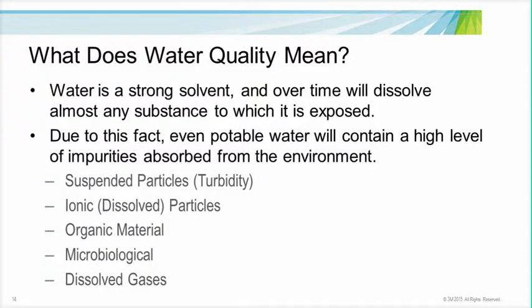In the healthcare industry, when we talk of water quality, we are referring to water with a reduced level of impurities as that of potable or drinking water. Because of its strong solvent characteristics, water inherently contains a myriad of impurities absorbed from the environment. We categorize these impurities as suspended particles, ionic or dissolved particles, organic material, microbiological in nature, and finally dissolved gases. Specifically, suspended particles include silt, clay, and decomposed organic matter, and are often referred to as turbidity due to the visual cloudiness observed. Ionic or dissolved particles, also known as total dissolved solids, refers primarily to those scaling metals such as calcium and magnesium, but may also include iron, manganese, as well as ionized salts.